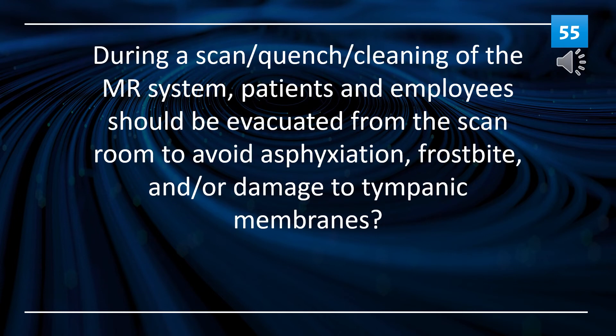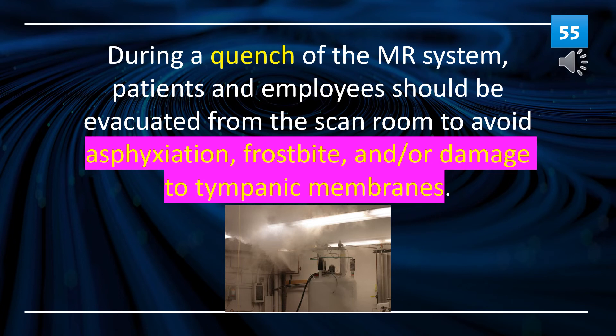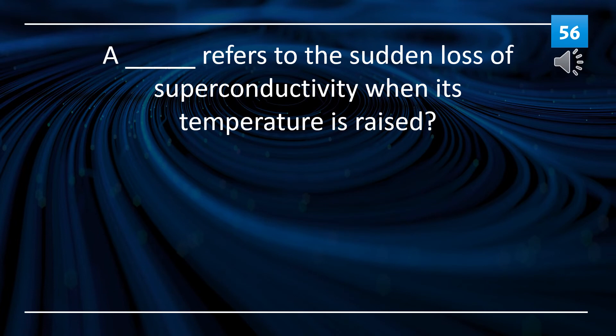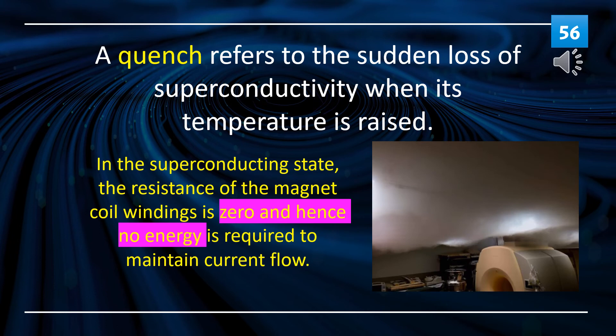During a scan quench or venting of the MR system, patients and employees should be evacuated from the scan room to avoid asphyxiation, frostbite, and/or damage to tympanic membranes. A quench refers to the sudden loss of superconductivity when its temperature is raised.